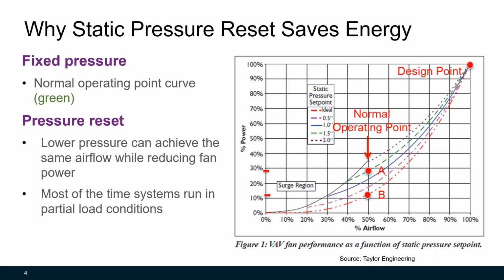Most of the time, the fan will run at partial load conditions, and at partial load conditions, the fan power can be greatly reduced if the static pressure can be reset lower. For example, at 50% of airflow, if the air handling unit static pressure is set at 1.5 inches, the fan power is around 28% of full power. But if we can reduce the static pressure to about 0.5 or lower, the fan power can be greatly reduced. That's the difference between point A and point B in this chart. In this project, the tiered trim and response method was used to reset the static pressure.